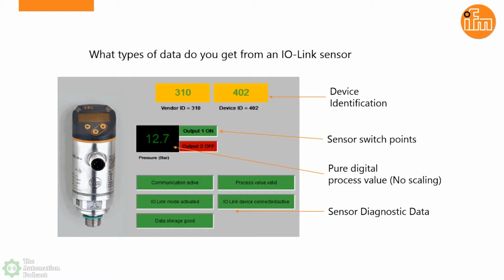So instead of receiving a 4 to 20 milliamp signal, which back in the PLC you'd see as maybe a 4,000 to 20,000 value, you'd then have to scale it and do the math to relate it to some kind of bar or PSI rating. You don't have to do any of that with IOLink—you actually get the actual measured value.